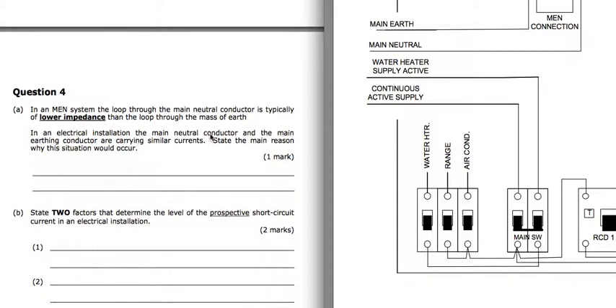Now in this one, the main neutral conductor and the main earthing conductor are carrying similar currents. State the main reason why this situation would occur. So there's going to be something wrong with this neutral conductor if it's only carrying the same amount of current as that through the Earth. And what they're saying there is there's a high resistance joint in the main neutral conductor.